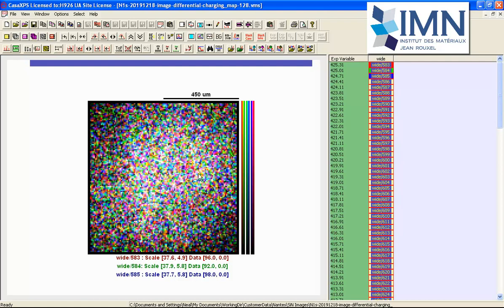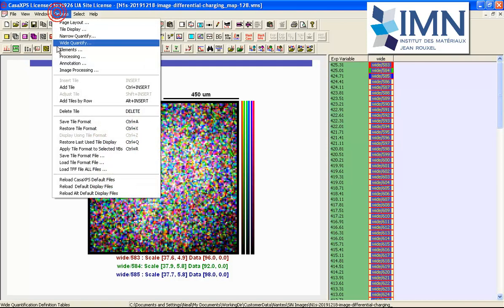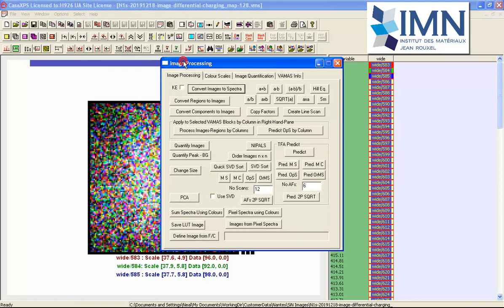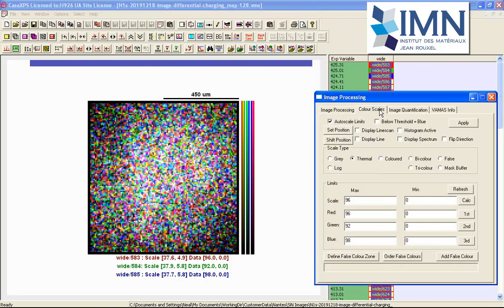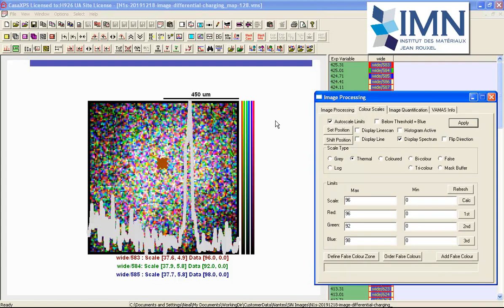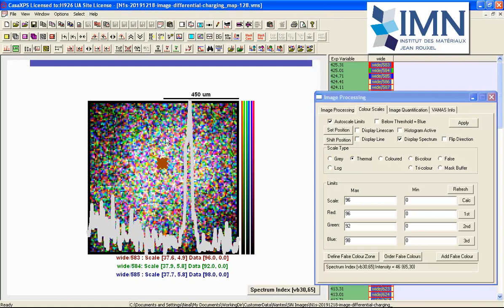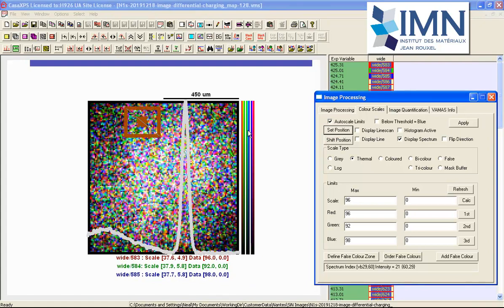All of these numbers down here represent binding energies and each one of these VAMAS blocks represents an image. You can see there is no obvious spatial information in these images. Nevertheless, if we go to the image processing dialogue window and go to the color scales property page and select display spectrum, when activated there is a point indicating where a spectrum is being calculated from these images.